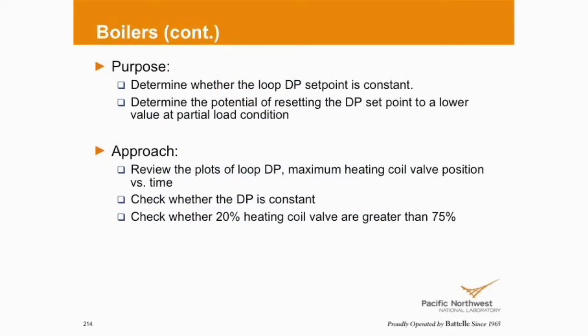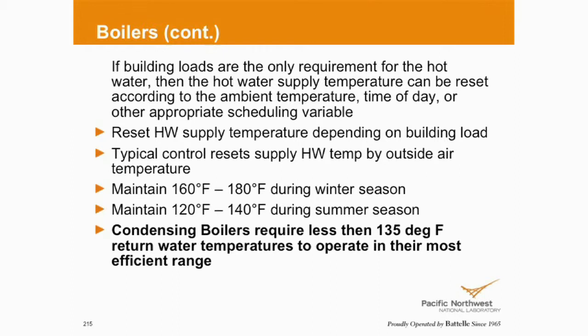So when we're looking at the trended data, we want to look to see if the differential pressure set point is constant. Does it vary based on some feedback, whether it's outdoor air or zone valves? If we're looking at hot water temperature resets, do we see a constant 160 to 180? Can we drop it during the summer? Condensing boilers are a huge opportunity. How many people have condensing boilers?